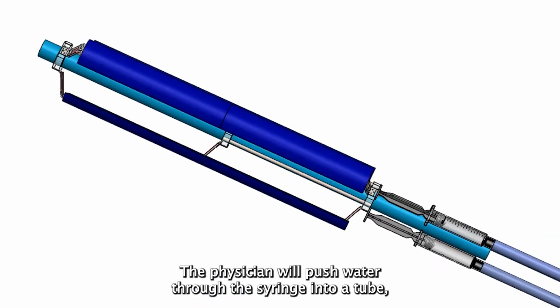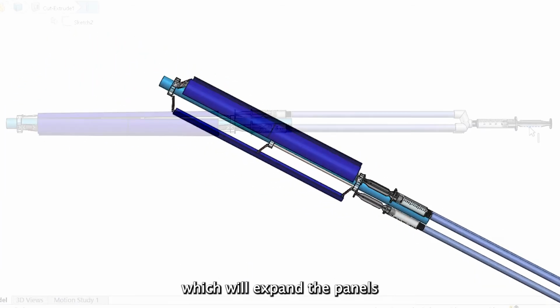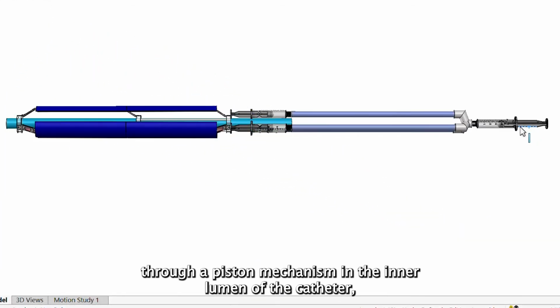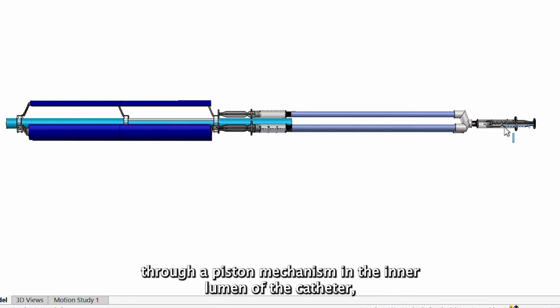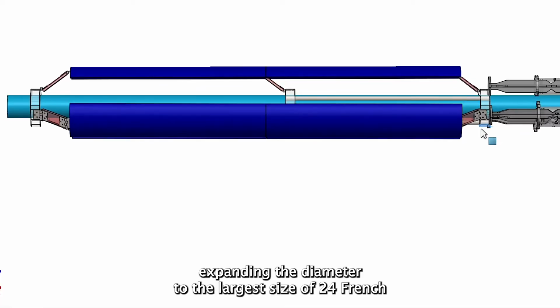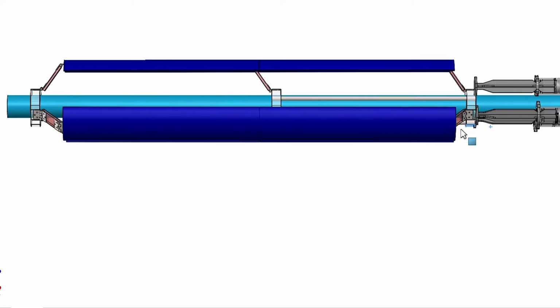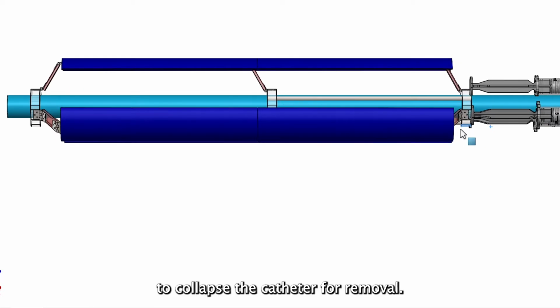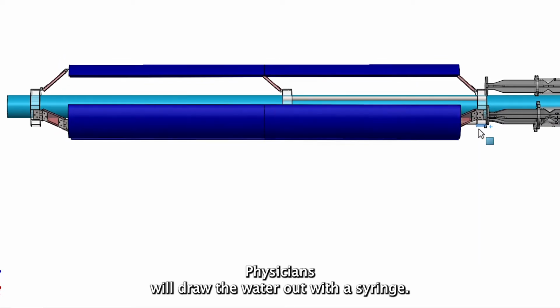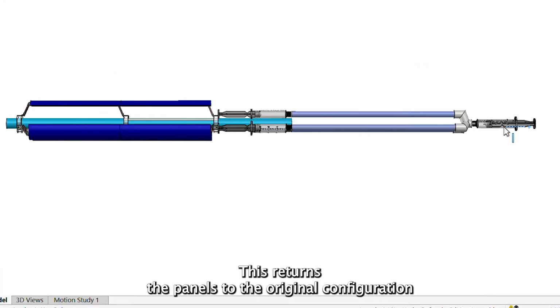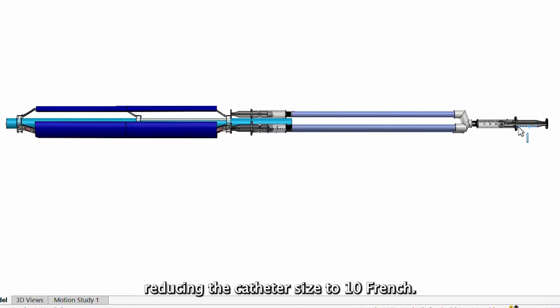The physician will push water through the syringe into a tube which will expand the panels through a piston mechanism in the inner lumen of the catheter, expanding the diameter to the largest size of 24 French. To collapse the catheter for removal, physicians will draw the water out with a syringe. This returns the panels to the original configuration, reducing the catheter size to 10 French.